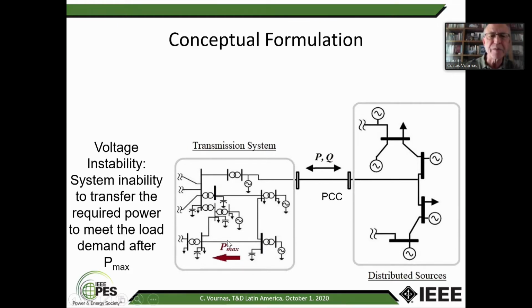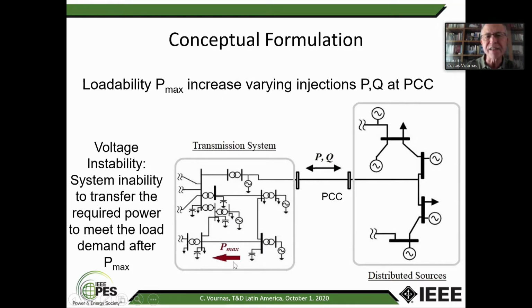So we have a power system that is experiencing a maximum power at some corridor, and the question is how we can increase this maximum loadability Pmax by varying the P and Q, the active and reactive power at the point of common coupling of various distributed sources. This is the structure of the problem. In my case, the distributed sources, as I said, are dedicated feeders connecting wind farms to the transmission system. And we have no control over the P. I will give cases where it is either constant or variable, but based on a probabilistic phenomenon, so it's stochastic or constant. But we can vary the reactive power through the controls of the feeders.